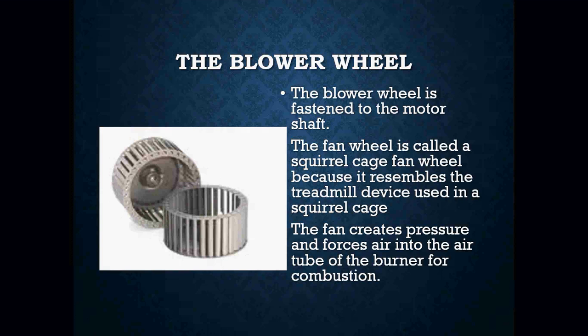The blower wheel is fastened to your motor shaft. The fan wheel can also be called a squirrel cage fan wheel because it resembles a treadmill device used in a squirrel cage. The fan creates pressure and forces air into the air tube of the burner to help support combustion. When servicing oil burners, we want to make sure that the blower wheel is nice and clean and not caked up with dirt and grime, because that will affect the way the burner actually operates.